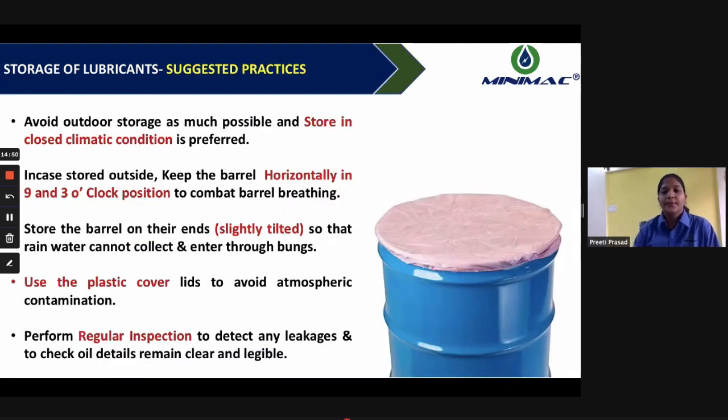So what do we suggest? The first suggestion is, of course, you should store the lubricant in a closed climatic condition as much as possible. In case you don't have that facility at your plant, and you are using outside storage, we must follow some points: the barrel should be kept in the 9 to 3 o'clock position to combat the barrel breathing, so that the oil is behind the bungs and the breathing is stopped.